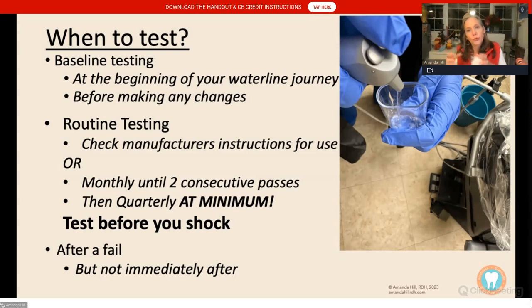Then test routinely. First, look at your chair manufacturer — some say monthly, some say quarterly. If they don't say anything, follow your treatment product recommendations. If they don't say anything either, OSAP — the Organization for Safety, Asepsis and Prevention — says to test monthly for two consecutive passes, and then go to quarterly testing. Once you've been passing for a while, quarterly testing is a perfect way to make sure your water lines are staying safe.